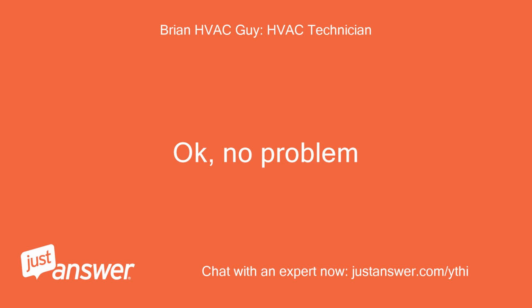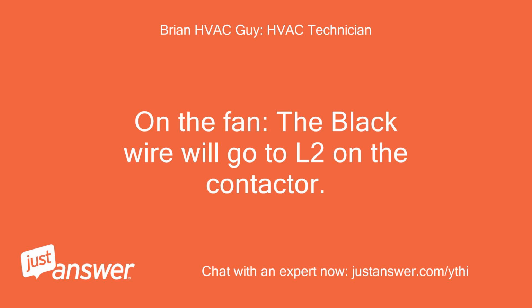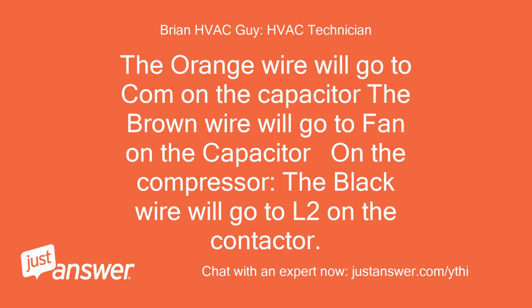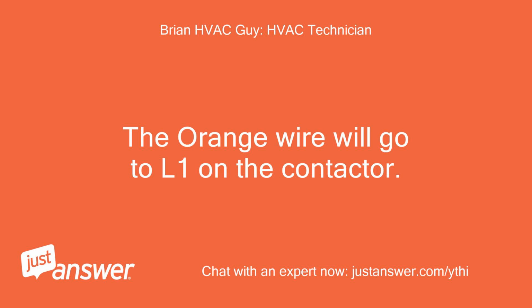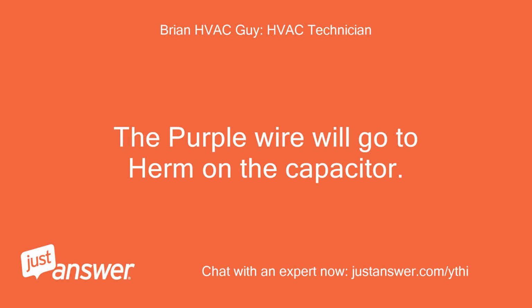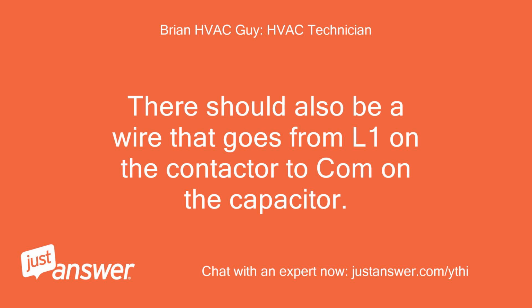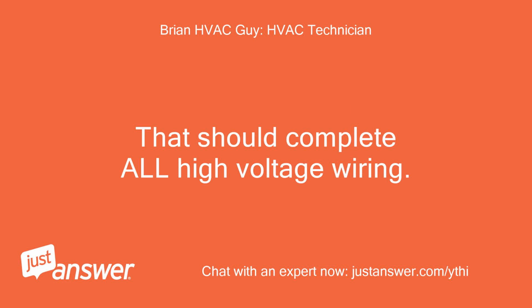Okay, no problem. On the fan, the black wire will go to L2 on the contactor. The orange wire will go to COM on the capacitor, the brown wire will go to fan on the capacitor. On the compressor, the black wire will go to L2 on the contactor. The orange wire will go to L1 on the contactor. The purple wire will go to HERM on the capacitor. There should also be a wire that goes from L1 on the contactor to COM on the capacitor. That should complete all high voltage wiring.